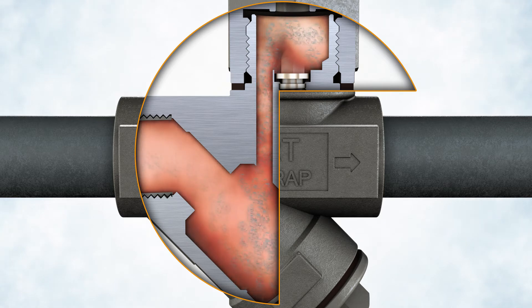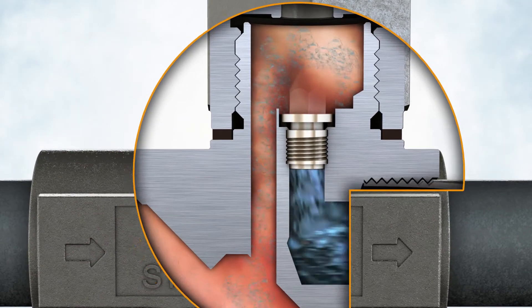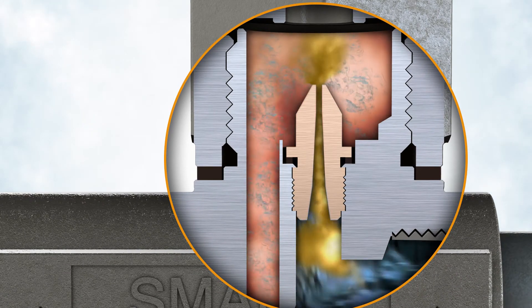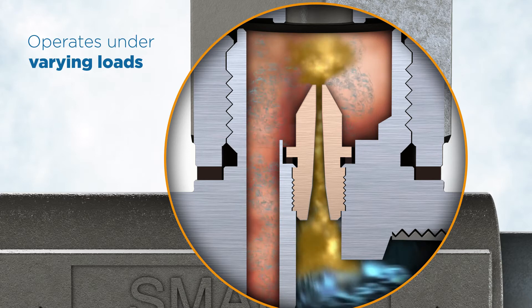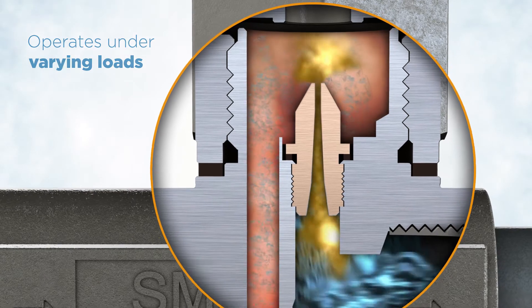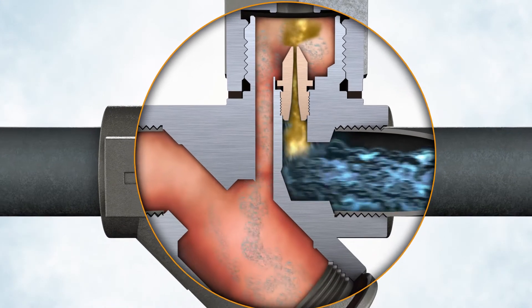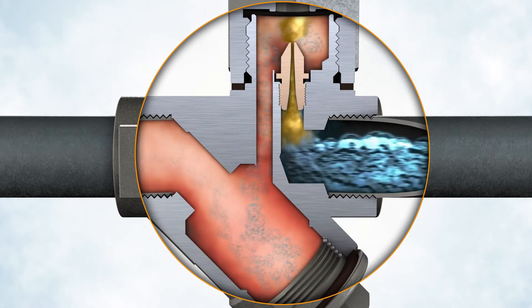barrier to the live steam. The higher the pressure differential is across the trap, the more condensate is converted to flash steam, allowing the venturi trap to operate correctly under varying loads.